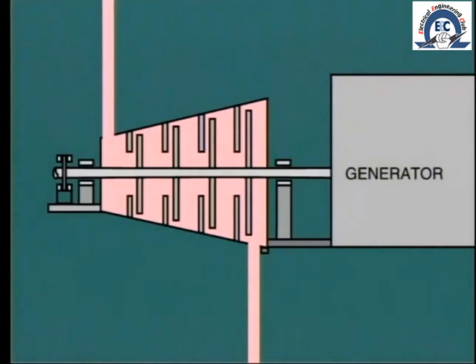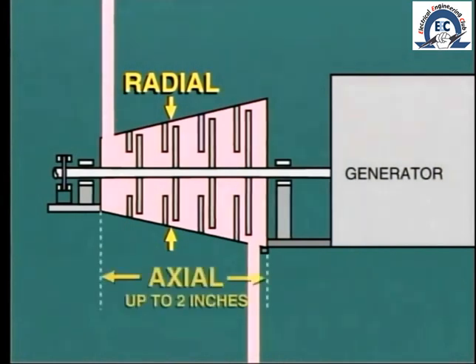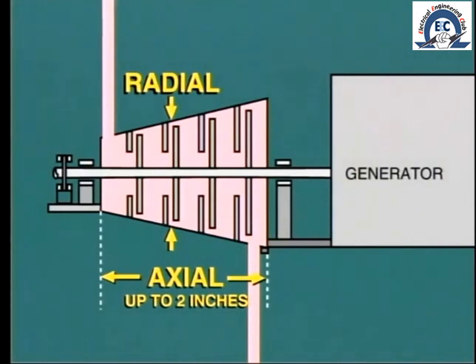In actual fact, the expansion of the turbine components in the radial direction is quite small. On the other hand, the longitudinal expansion — that is, in the axial direction — is considerable, perhaps 1 to 2 inches between the cold and full load condition.